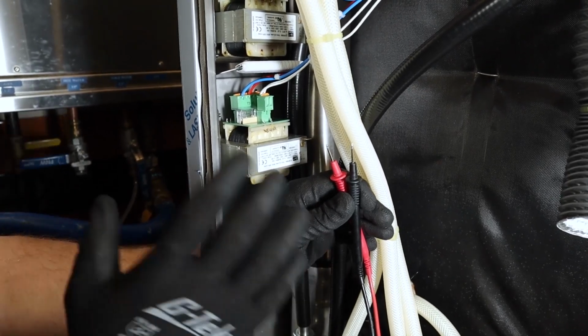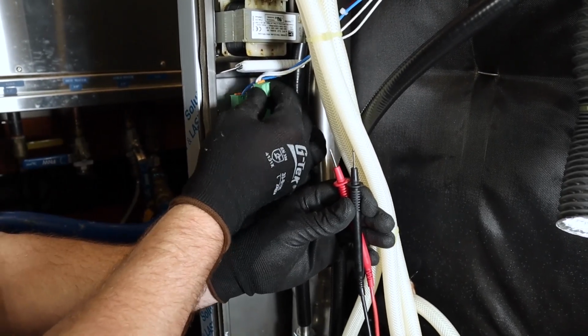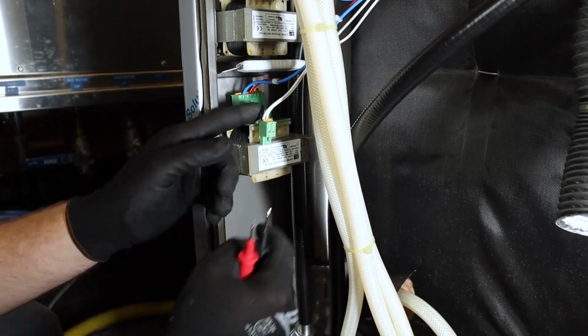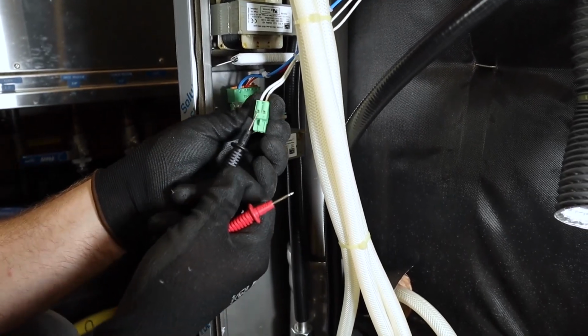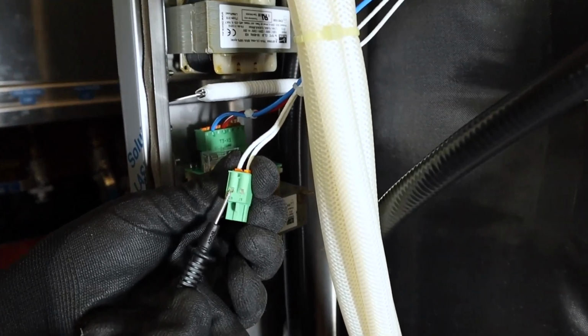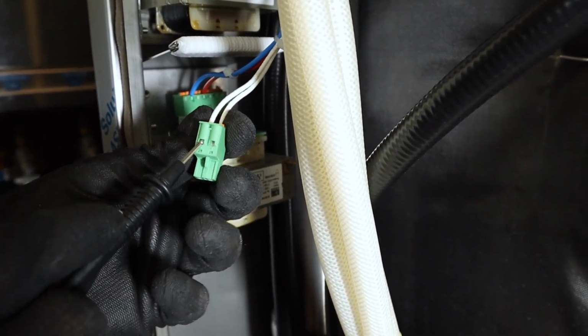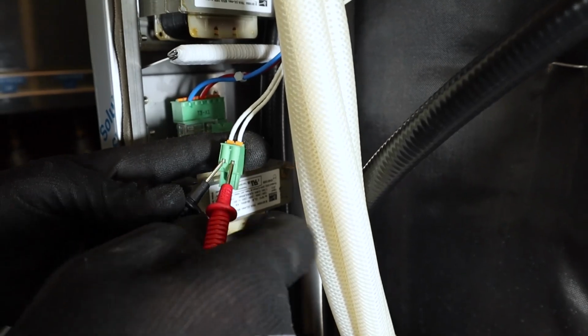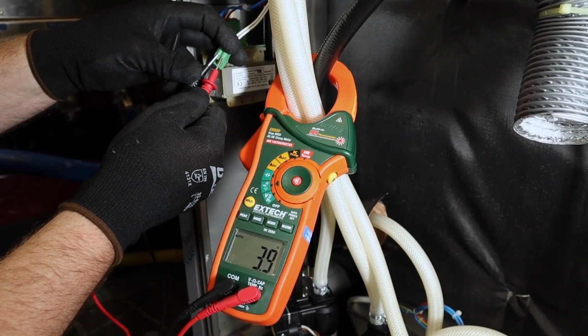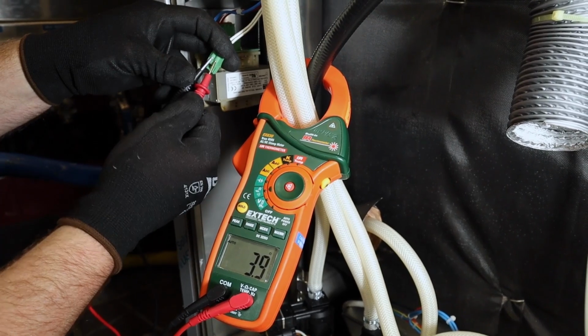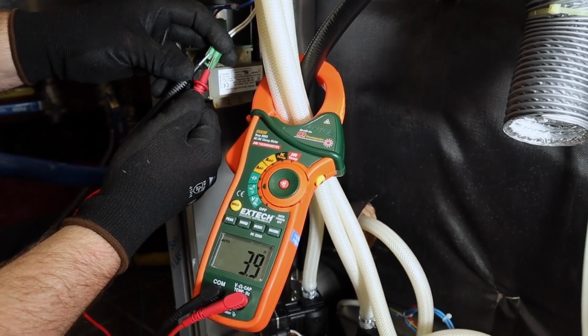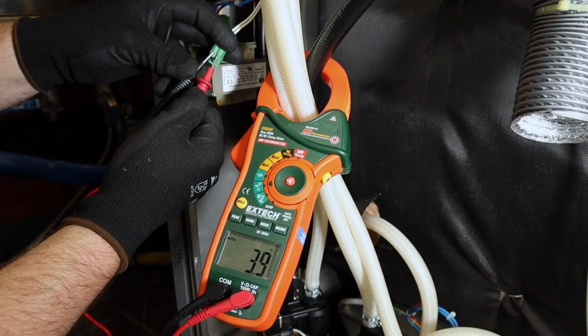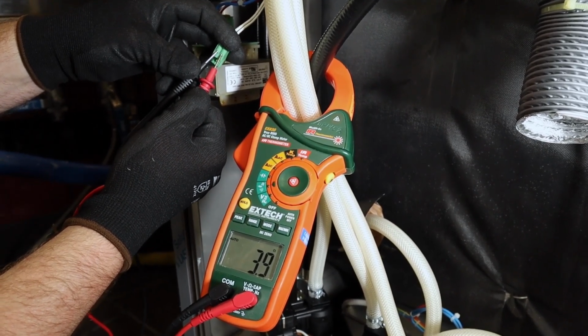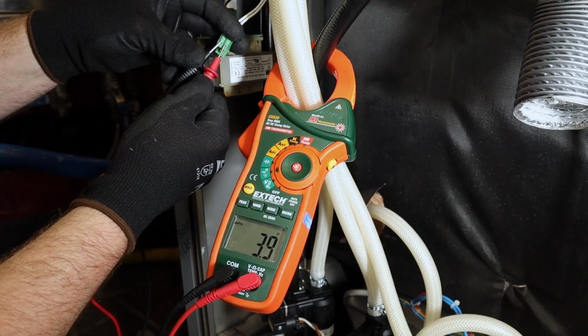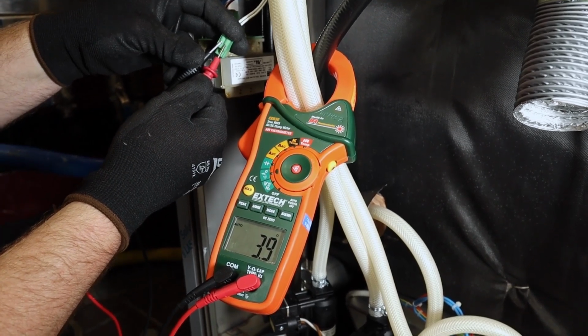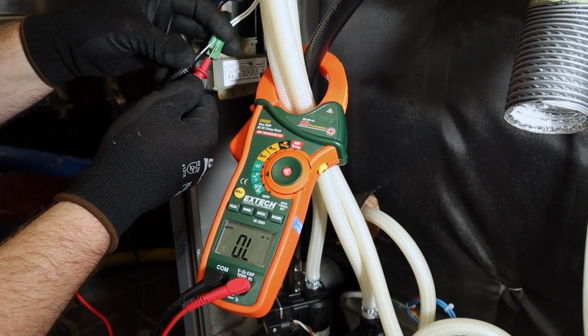But in this instance, what I was talking about when checking the unit cold for our glow electrode is we're going to unplug it like so, and then you have these nice little conductive pieces right here on the side of the connector that we're going to put our meter leads in so we can check our resistance. Now for resistance, we are looking for 1 to 6 ohms when we check this. So now with this unit cold, like I mentioned before, we've checked our resistance and you can see that we have 3.9 ohms. That range that we're looking for is 1 to 6. So this glow electrode would be good.